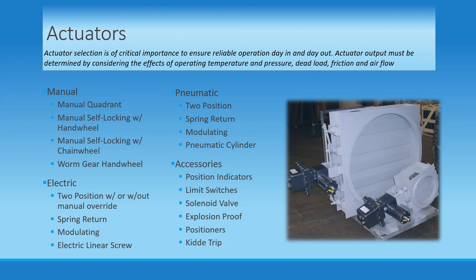Manual operators use human power, often with a mechanical multiplier, to open, close, and position a damper. The simplest is a manual quadrant — a lever welded to the drive axle allowing the axle to be turned. Industrial quadrants come with locking mechanisms to ensure the damper remains in the proper position. Hand wheel and chain wheel manual operators ensure easy operation with a locking mechanism, either through chain pull and pulley operation or direct drive to the axle. Worm gear operators are used for heavy torque conditions where multiplication of manual input force is necessary, with the added benefit of being self-locking.